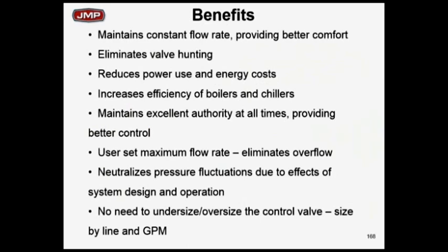Great benefits. We went through the whole issue, and I don't want to bore you too much. You can read them right here, but we can maintain constant flow as I change the differential pressure. As I change the differential pressure, I can prevent valve hunting. I can reduce power and energy costs because I'm giving you a high delta T. I increase the efficiencies of the boilers and the chillers as I increase your delta T. I don't worry about valve authority, really. The pressure independent control valve takes care of it. I can just pick them on GPM. You can set the max flow through them. It takes all those differential pressure effects in my system and neutralizes them, so I don't have to worry about them. Bottom line, you can pick them on GPM. You don't have to worry about the Cv of the valve so much.